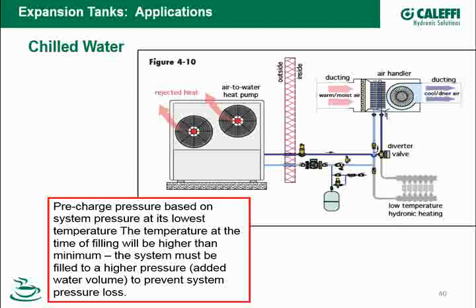So on fill with chilled water, one of the things that has to be calculated is, when I'm filling the system based on the temperature, how much extra water I need to put into the expansion tank so that when the system drops down to its operating temperature, I don't lose pressure. If I have a way of metering it, it's probably going to be done by adding additional volume of water. If I'm not metering the fill, I may have to do it based on calculating a final pressure.